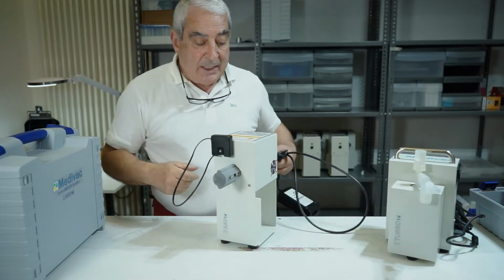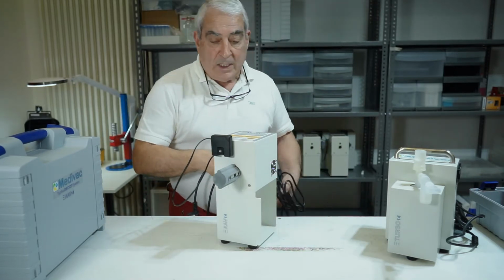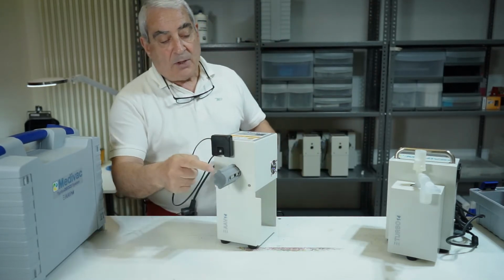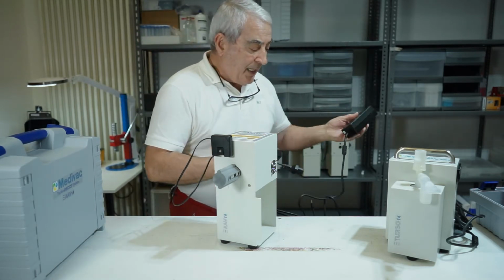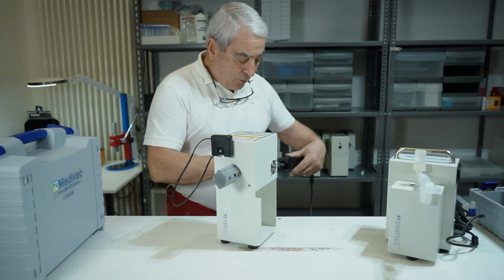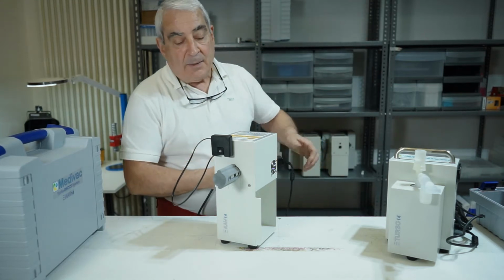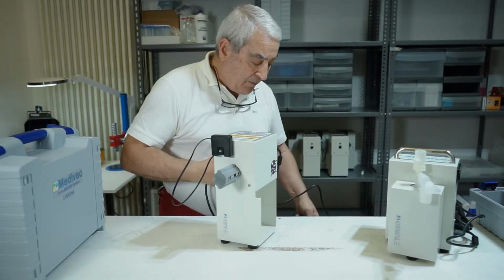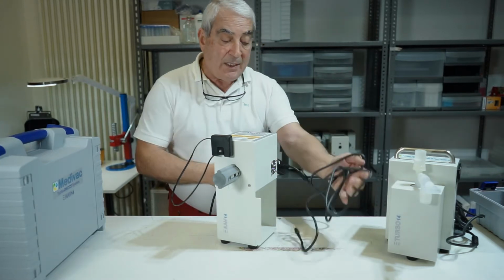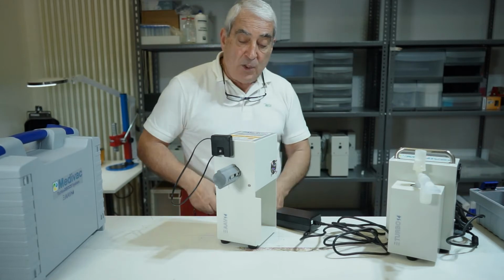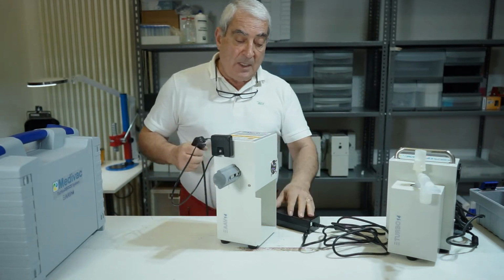The AAV consists of a steel structure carrying a mechanical actuator suitable to open and close, alternatively, a channel of the collection circuit, depending on the CO2 concentration.